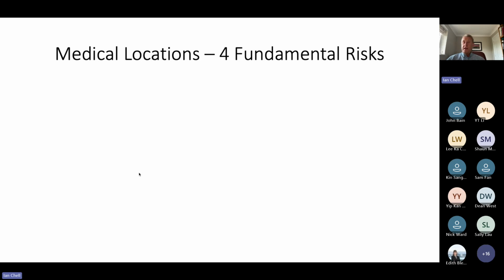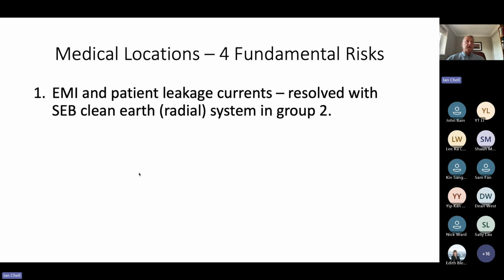So moving on, I want to explain now how I teach the risks in medical locations. Okay. So risk number one that you have to mitigate is EMI and patient leakage currents. And that's resolved with the supplementary equipotential bonding clean earth system, which is radial in a group 2. So hopefully you all understand that. And if that's not done properly, then you're not minimizing the risks. This is why the IT guidance needs to be followed explicitly.